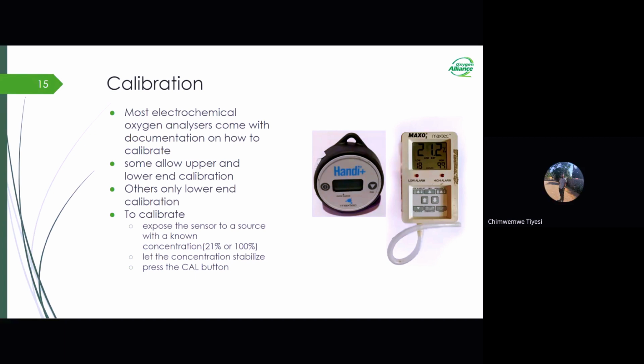If your analyzer has buttons which allow you to increase or decrease the concentration, you can do this. You know that room air has 21% oxygen. So if you're exposed to 21% oxygen, you reduce or increase so that the analyzer will show 21. Then you lock it. At that point, you have calibrated. The same will work when you are calibrating at 100%. Then you have analyzers that only work for the lower end. You can just expose them to room air. When they hit 21%, you hit the calibration button. It's done, and that's all.